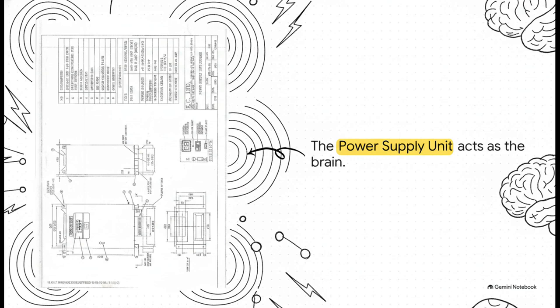But as you can guess, muscle and senses are totally useless without a brain to coordinate them. Enter the Combined Power Supply Unit, or PSU, taking in a standard AC 440-volt power feed directly from the ship's generators. This sophisticated unit converts it and pushes out a maximum of 350 amps at 24 volts DC. It also features a touchscreen LCD panel on the front, giving the engineering crew instant access to reference cell potentials, output current, voltage, and all alarm statuses. Simply put, this cabinet is where all the decision-making happens.